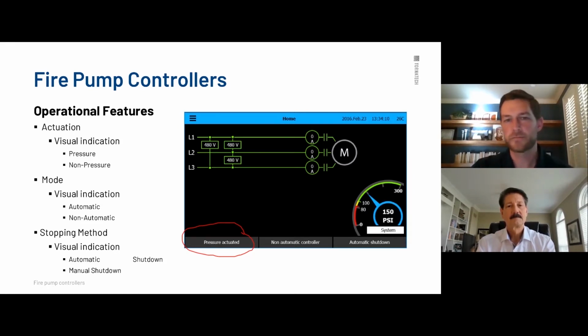If it's non-pressure, like a foam system or something like that, it would say non-pressure there instead of pressure actuated. We also have to show if it's an automatic or a non-automatic controller. For some reason, this controller is actually set up to be non-automatic. So even if it is pressure actuated, it's not coming on automatically. That's just the way this demo or this screen is set. Typically, it says automatic controller, meaning it's going to come on automatically with a pressure drop.